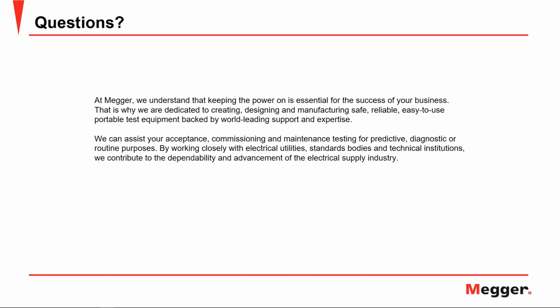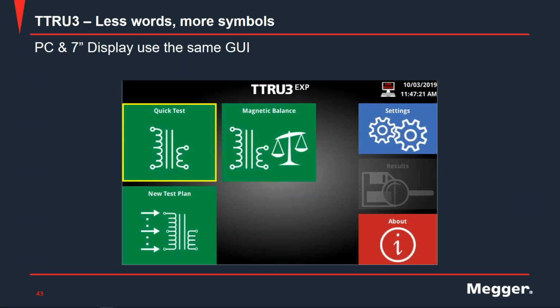So I believe you're referring to the results that you would get from the testing that you perform. In the version of the software that we're preparing to release, we have added a setting that would allow you to view phase deviation from a relative phase position. So we're talking about phase deviation relative to DYN1. DYN1 is a 30-degree phase shift.